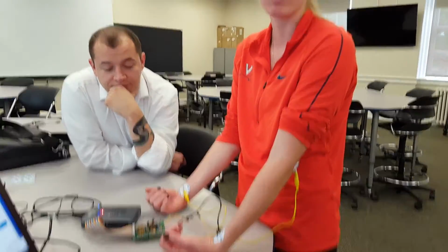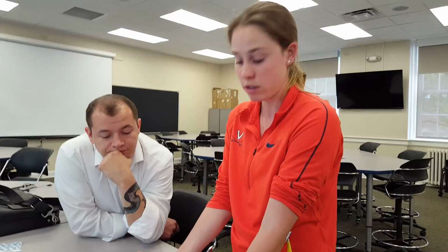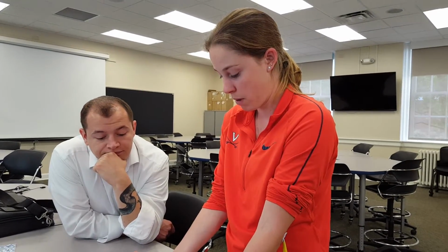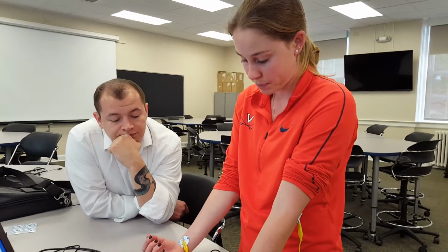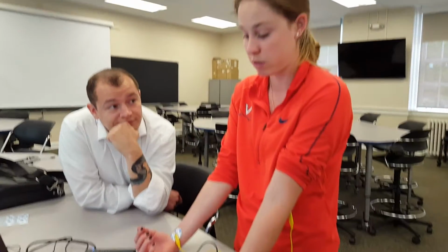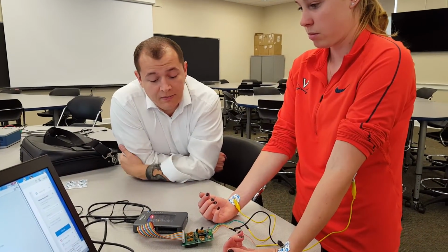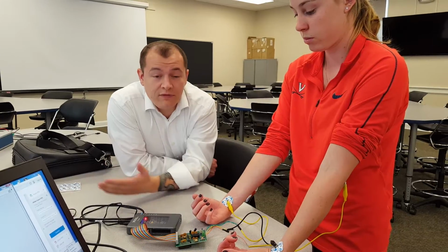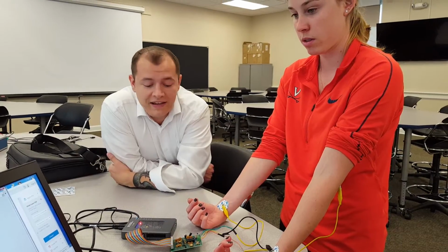The noise we're mainly trying to filter out is 60 hertz noise. That's just present because that's what voltage at the power outlets runs at. And so we have a filter that has a breakpoint of 500 hertz, and we have it filtering out both a positive and a negative signal. And then we're referencing ground to a bone here, which is my elbow, just assuming that there will be no signals there. One of the reasons that we chose 500 hertz was because we looked up in medical journals and found that most of the frequencies that we would be sampling were right about that, right in that frequency range.